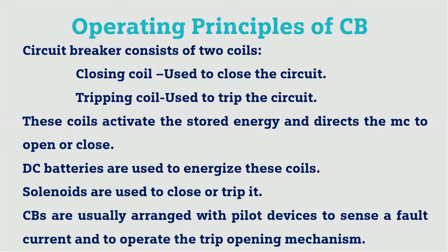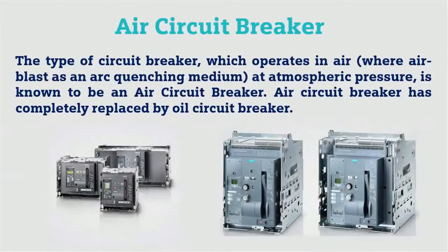Solenoids are used to close or trip the contacts. Circuit breakers are usually arranged with pilot devices to sense the fault current and operate the opening mechanism. An air circuit breaker is the type of circuit breaker that operates in air, where air blast acts as the arc quenching medium at atmospheric pressure. Nowadays, oil circuit breakers have been largely replaced by ACBs.